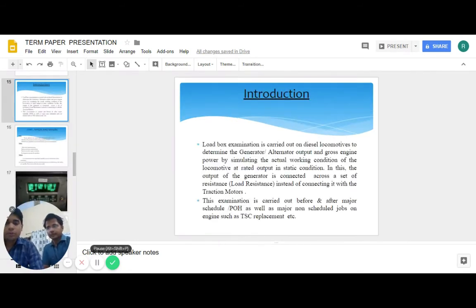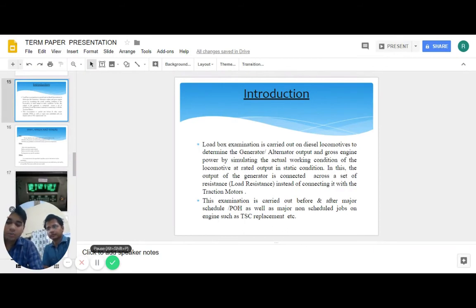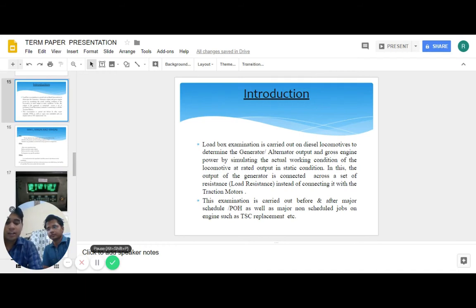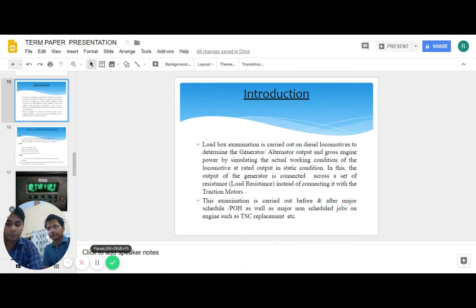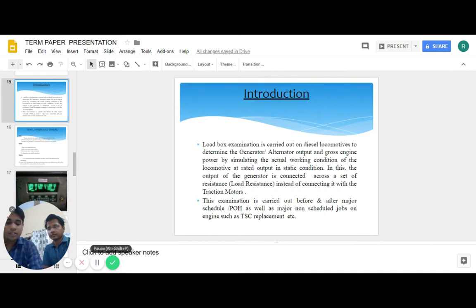Let me introduce you to load box testing. This is a test to check the capability and performance of the engine by simulating the actual working condition of the locomotive at rated output in static condition. Load box examination is carried out in diesel locomotives to determine the generator alternator output and the gross engine power. The output of generator is connected across a set of resistances instead of connecting it with the traction motor. This examination is carried out before and after major scheduled POH as well as major non-scheduled jobs on engines such as TSC replacement.